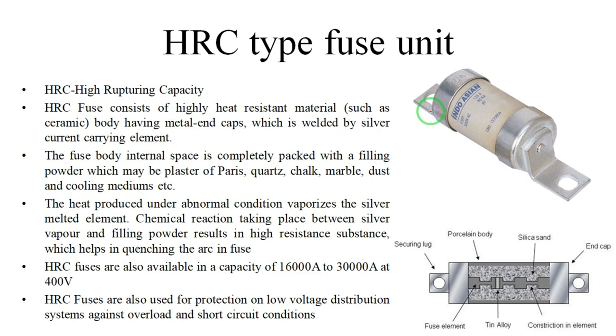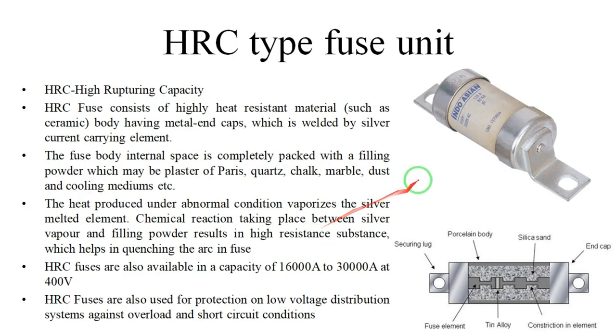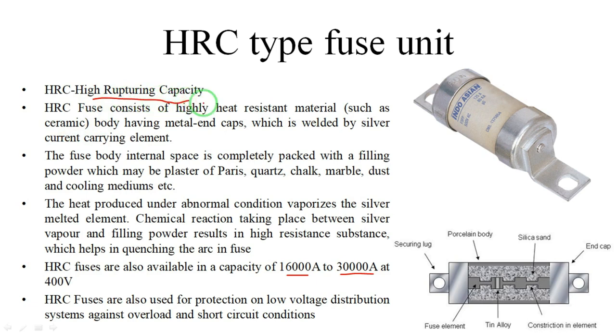The third type is the HRC type fuse. HRC means High Rupturing Capacity. This fuse also looks like a cartridge type fuse, but the difference is the current rating — the cartridge fuse is rated at 600 amperes, while the HRC fuse has a large current capacity of 16,000 to 30,000 amperes at 400 volts. The fuse consists of a highly heat-resistant body with metal end caps and two silver connectors. The internal space of the fuse body is completely packed with a filling powder.